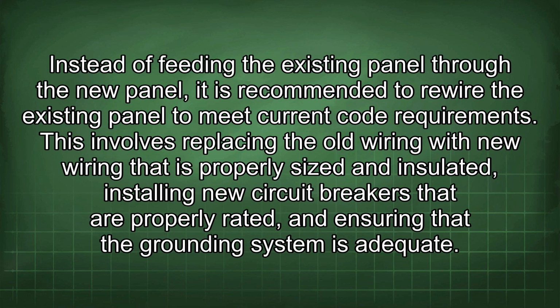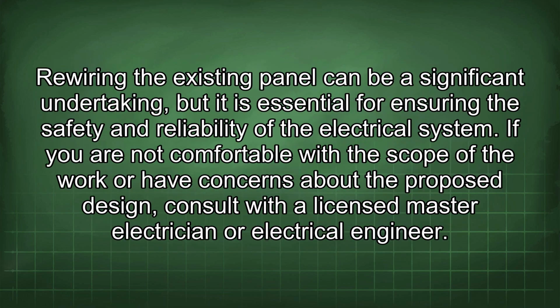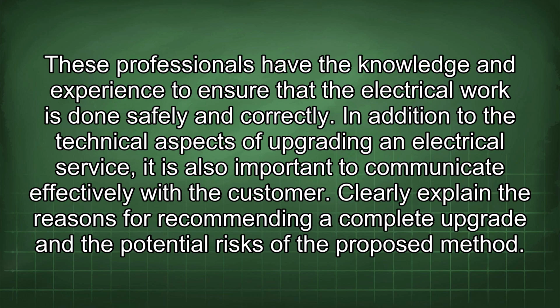Instead of feeding the existing panel through the new panel, it is recommended to rewire the existing panel to meet current code requirements. This involves replacing the old wiring with new wiring that is properly sized and insulated, installing new circuit breakers that are properly rated, and ensuring that the grounding system is adequate. Rewiring the existing panel can be a significant undertaking, but it is essential for ensuring the safety and reliability of the electrical system. If you are not comfortable with the scope of the work or have concerns about the proposed design, consult with a licensed master electrician or electrical engineer. These professionals have the knowledge and experience to ensure that the electrical work is done safely and correctly.